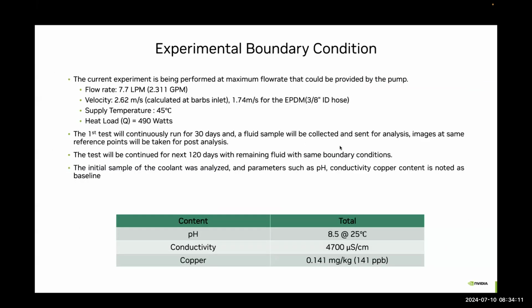We gave the single cold plate a flow rate of up to 7.7 lpm, which is 2.3 gpm. The velocity we achieve at the barb or inlet of the cold plate is 2.62 meters per second, which is much higher than the 1.5 meters per second in the literature, and we haven't been able to find any empirical data to support that claim. Similarly, in the EPDM hose we use for this setup, the velocity was 1.74 meters per second. The heat load we gave to the thermal test vehicle is around 490 watts.